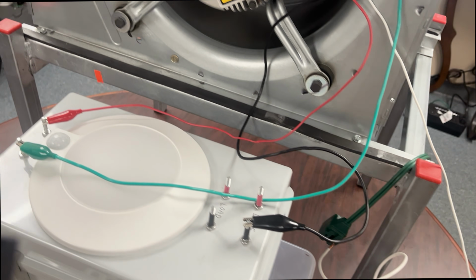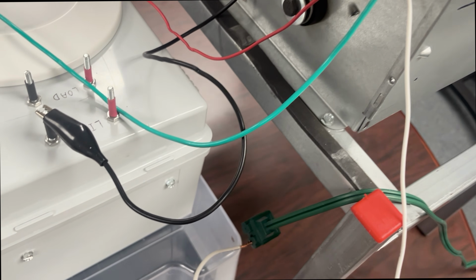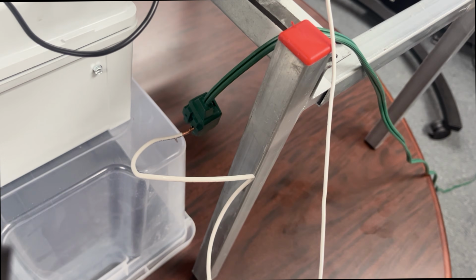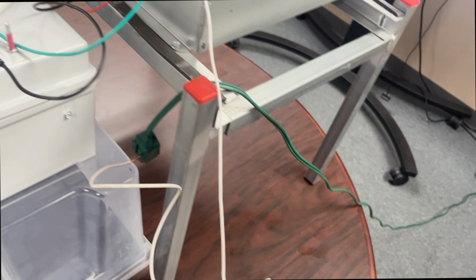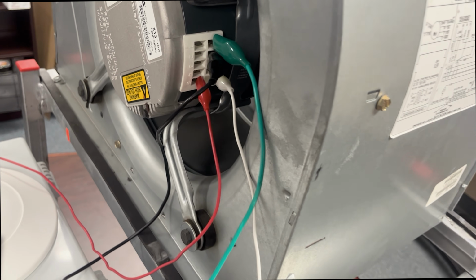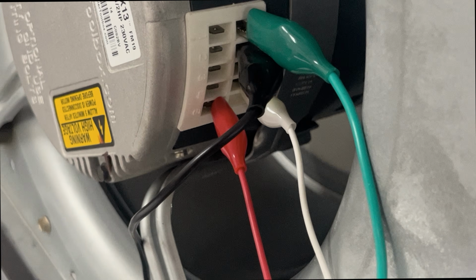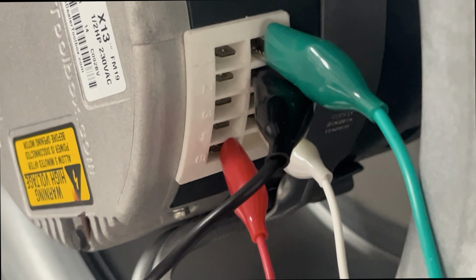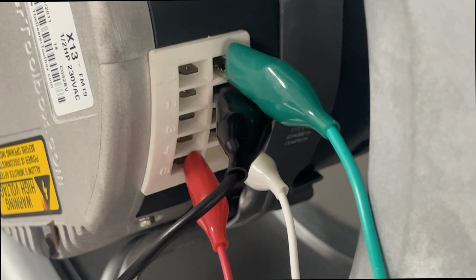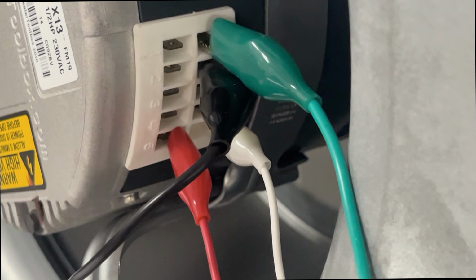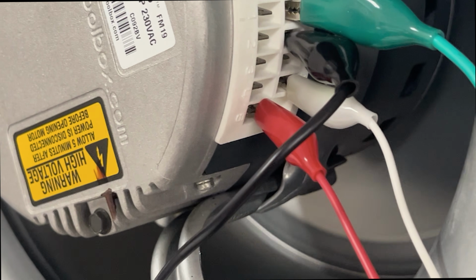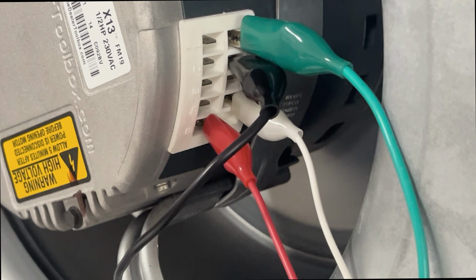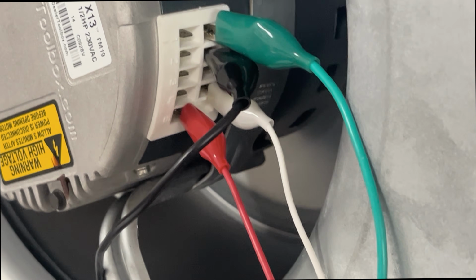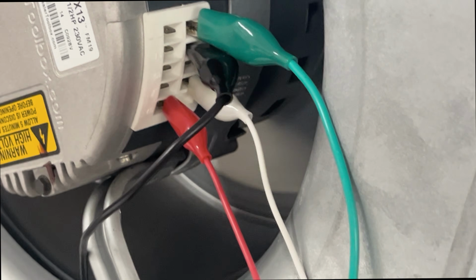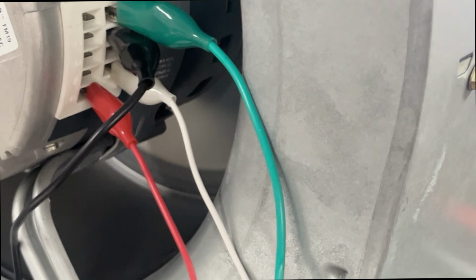We have R and C. We only have one line, okay? You can see the neutral is just sitting on the extension cord. And if I get in here and show you with the terminals, I got 5 wired up, and then I have common, which is the green wire, black, which is going to L, and then I have white down here, which is going in. And I'm using this for my N for neutral. That's why they have it labeled N, because it can be a second line voltage or it's just a path back. So this is just running on 115 volts right now.